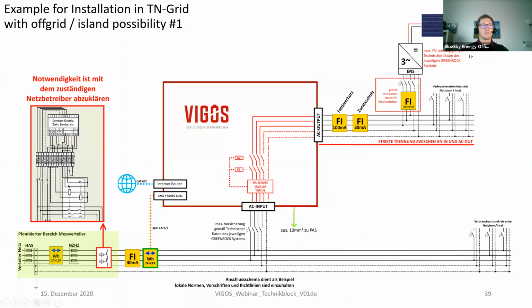So first, the system always takes a look at the loads, and only if the PV provides more power than the loads need, the battery starts charging. And it starts discharging as soon as the PV gives less than the loads need. In case of a grid failure, we disconnect here again. But as the Vigos is giving its own microgrid, the PV inverter has a grid where it can synchronize and connect. So then it will supply the loads and it will charge the batteries.